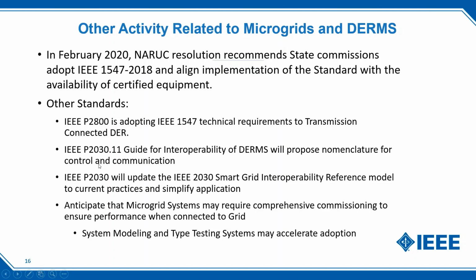There's other standards going on that are dealing with certain aspects of it. IEEE 2800 is adopting the 1547 requirements, but there's some unique things for inverter-based systems that are connected to the transmission system. And those are mainly large-scale solar and wind systems. 2030.11 is an interoperability guide for distributed energy resource management systems. And those are systems that could include aggregation systems from a third party or from a transmission operator or utility wanting to manage multiple distributed energy resources. We're actually waiting for approval from the standards board 2 weeks from now for the revision of the base 2030 smart grid standard. And if that gets approved, we'll start organizing meetings in May.